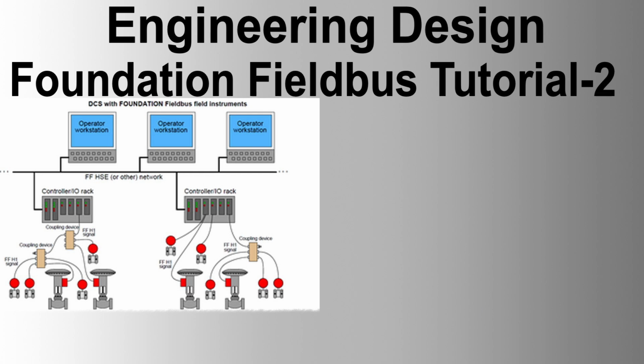Application time synchronization. Fieldbus applications need to be synchronized in the sense of time to interact with each other effectively. For example, an event message needs a timestamp to indicate when it is detected because it is received sometime later, depending on the token rotation and bus traffic. SMKP provides a mechanism for all management VFDs to share the synchronized time. This ensures that all devices and applications within the Fieldbus network operate in a coordinated and timely manner, which is crucial for maintaining the integrity and reliability of the control system.